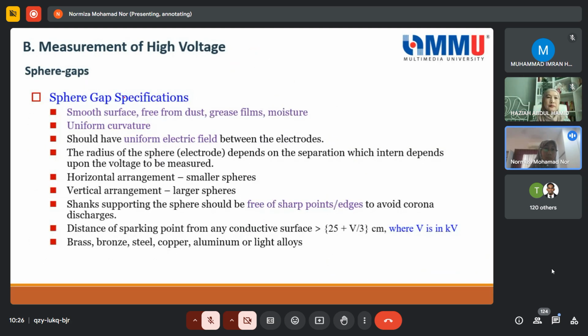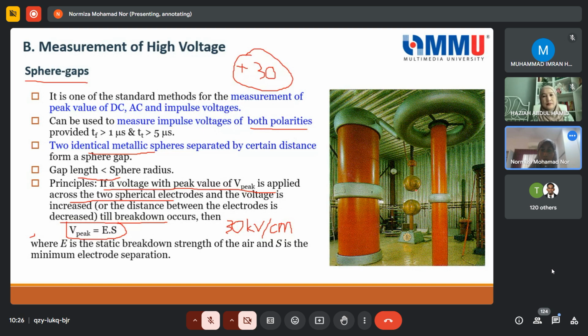Okay, the specification of the sphere gap is a smooth surface, free from dust, grease and moisture. You can see the construction here, it has to be smooth. It should not be dented, because if the ball is dented, the dent will give you a different electric field. When it is a smooth curvature, the electric field will be smooth, in other words uniform. But when you have a dent, the electric field will be very much distorted. That can of course give a high electric field at this point.